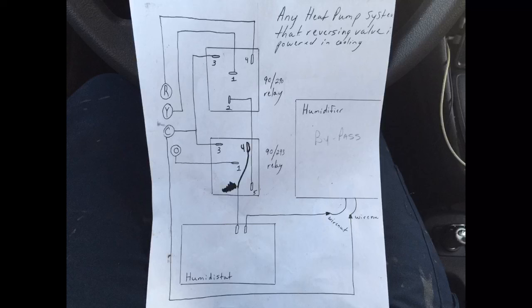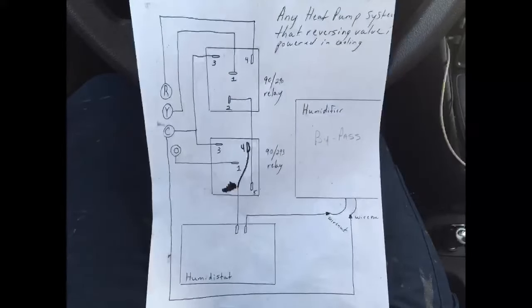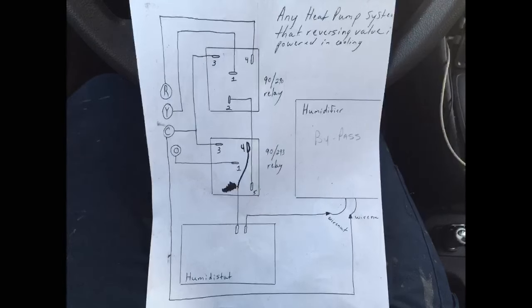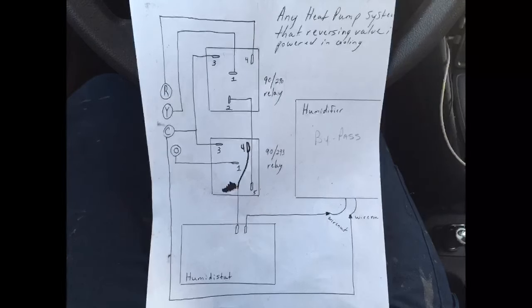The 9290 relay on the top has got 4 terminals on it. It's got terminal 1 and terminal 3, which is your 24 volt coil, and then you've got terminal 2 and terminal 4, which is your normally open. When you get power between Y and common, the cooling power on Y, that number 2 and number 4 set of contacts closes. When you lose power, those contacts open.